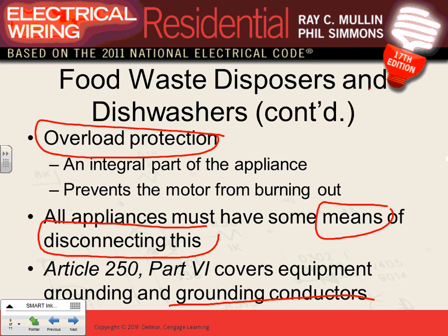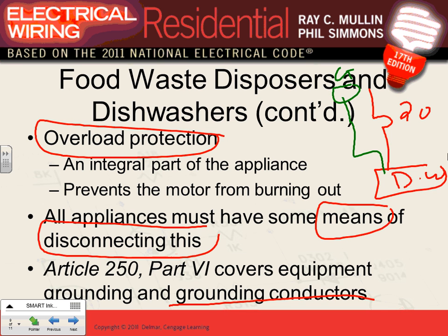So let's talk about, here's my 20 amp circuit. Here are my appliances, a dishwasher, let's say hardwired. You're going to bring a conductor here. This will be my ground. And I need to bring also a neutral. Here's my neutral. So the grounding conductor, typically this will be number 12 since you're wiring with cable, and these also will be number 12. Done. With every piece of equipment, you have to provide an equipment grounding conductor.